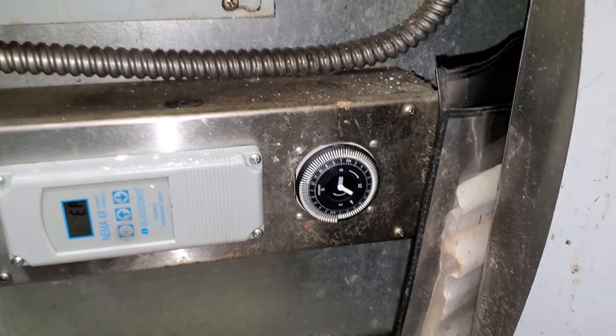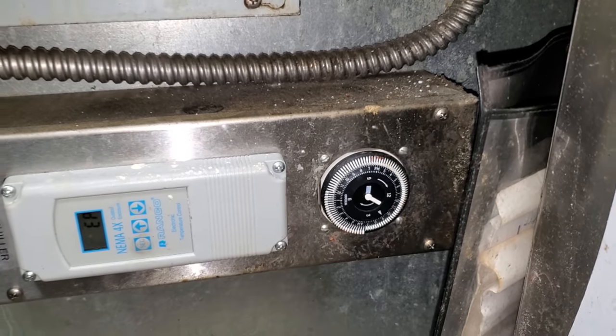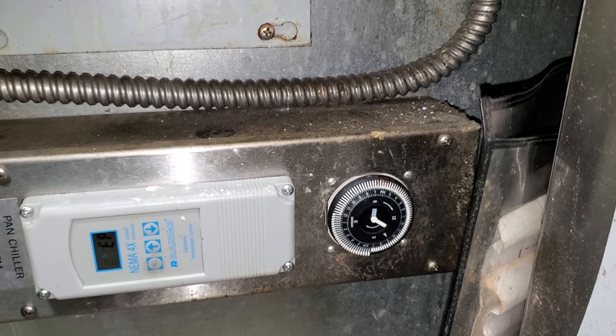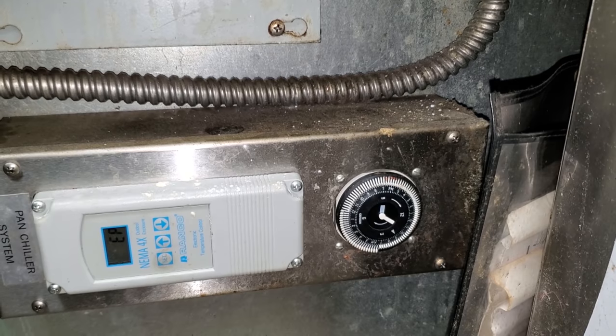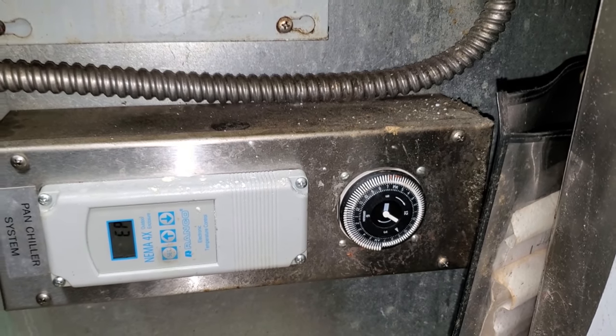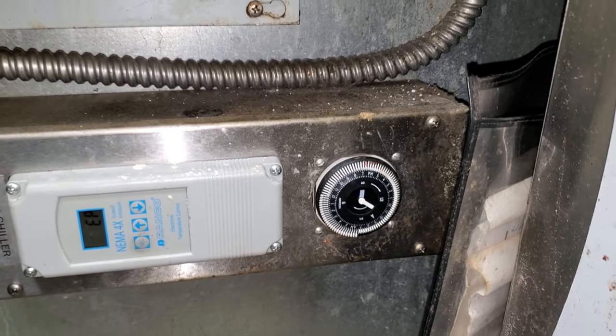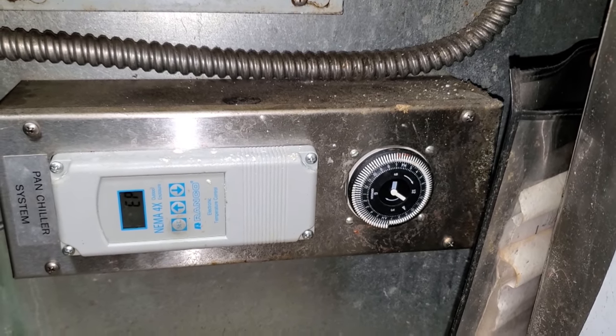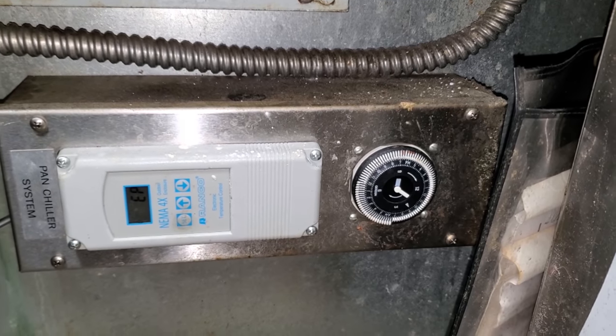It defrosts all night on the cold rail, but this timer has a battery backup built into it and it should never lose time. So it's very possible that it's bad, but on the flip side, we've got to wonder if they've been messing with it too.